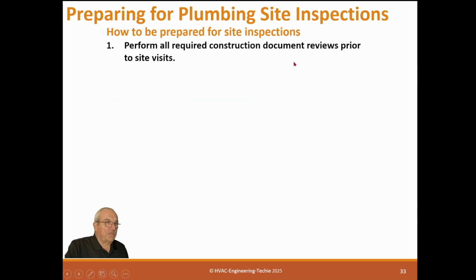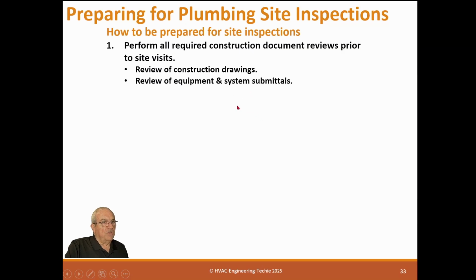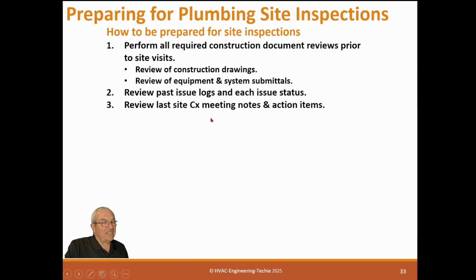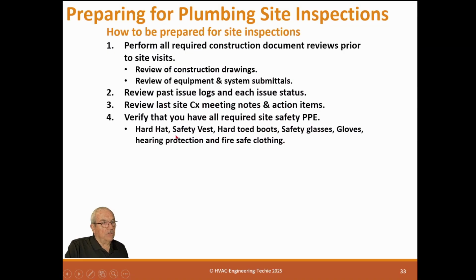How to be prepared for site inspections. Perform all required in construction document review prior to the site visit. Review of construction drawings. Review of equipment and system submittals. Review past issue logs and each issue status. Review last site CX meeting notes and action items. Verify that you have all required site safety PPE, including hard hats, safety vests, hard-toed boots, safety glasses, gloves, hearing protection, and fire-safe clothing, that you need to have every time you go there.